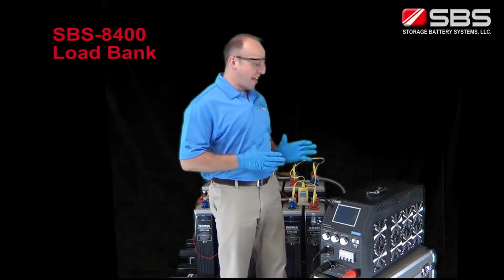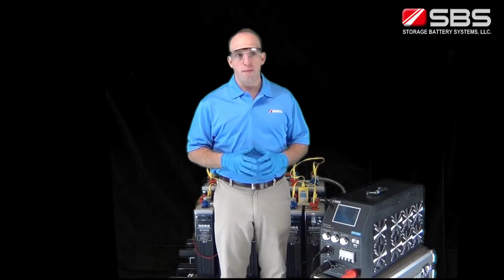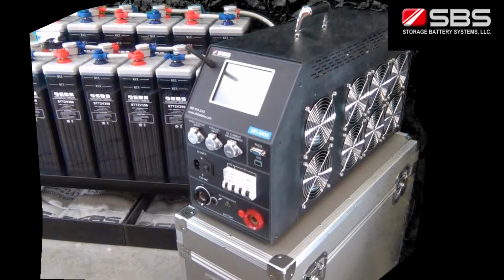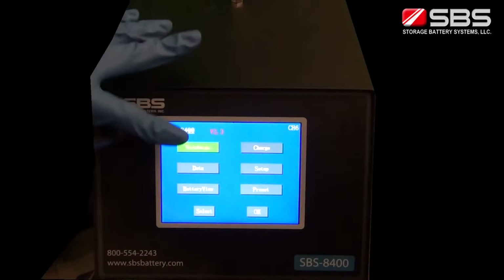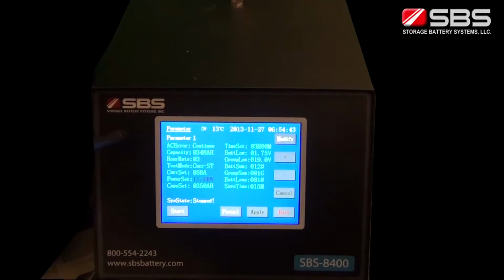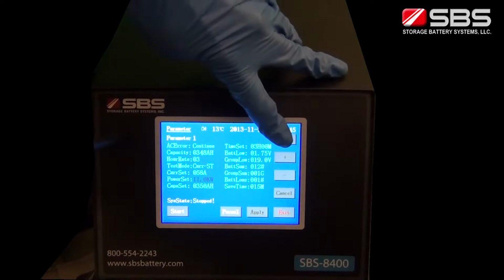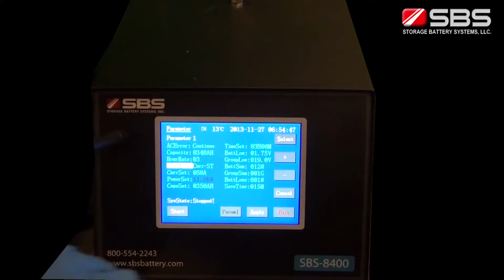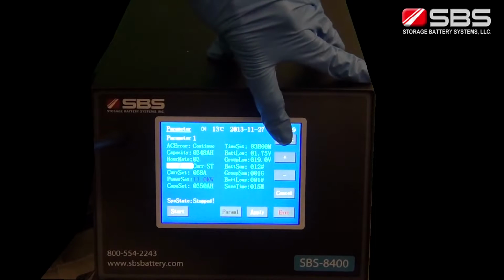Introducing the SBS-8400 load bank. Load bank testing is a way of verifying the correct operational performance and capacity of the battery system. The SBS-8400 load bank allows you to maintain compliance with NERC and IEEE standards. Programming and control of the SBS-8400 load bank is done on the color touchscreen LCD. The SBS-8400 load bank was designed to make testing of battery systems much more efficient.